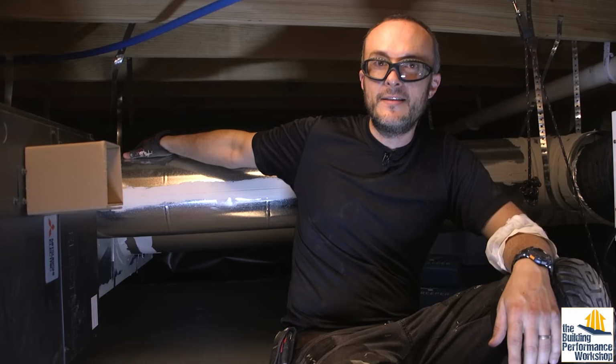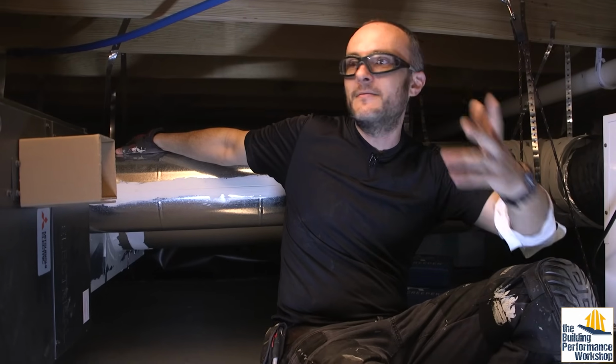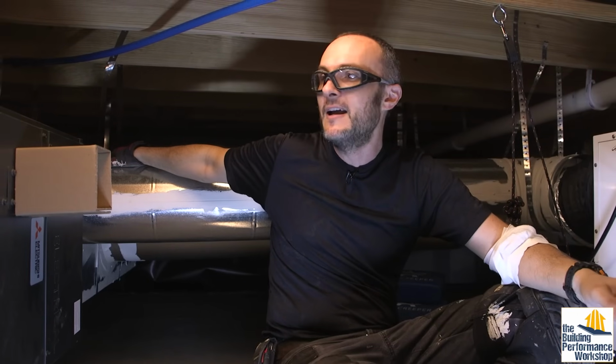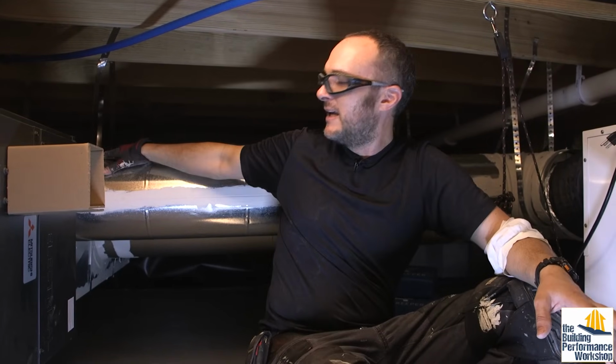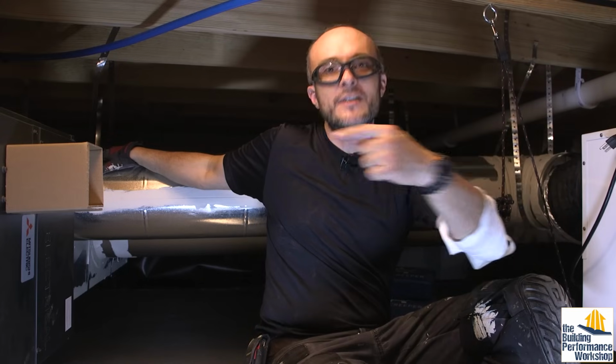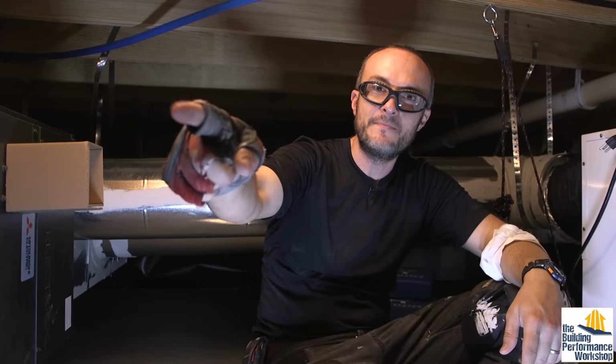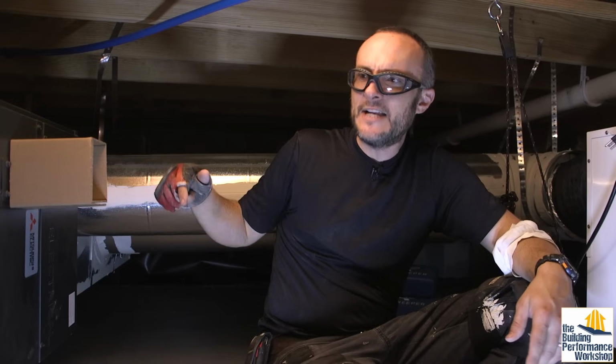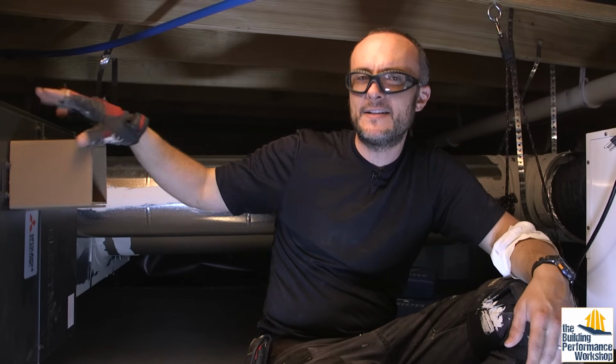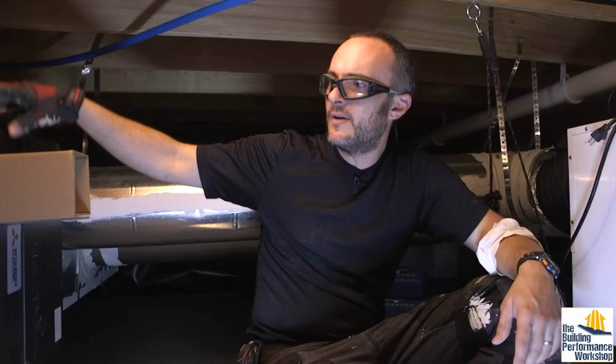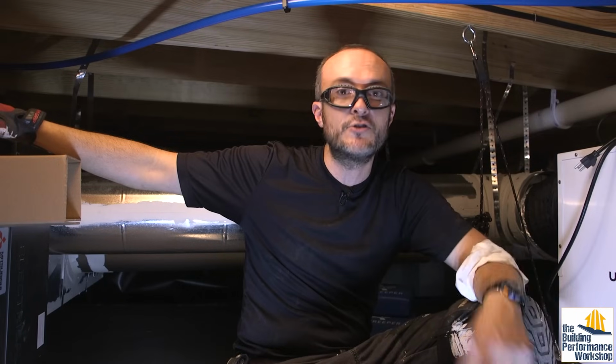I was not on the train of thinking that there was any good way to do this in particular that everyone agreed on, but it turns out that everybody has been wrong for the last 20 years. We've been plugging the dry side, the output of a dehumidifier, into the return, and then putting dry air through our equipment. Number one, it's hot air, and so it's going to make things a little bit weirder inside as far as mechanics of this, but it's also going to not allow the heat pump to do any dehumidification at all, because it's basically drying out any of that stuff.